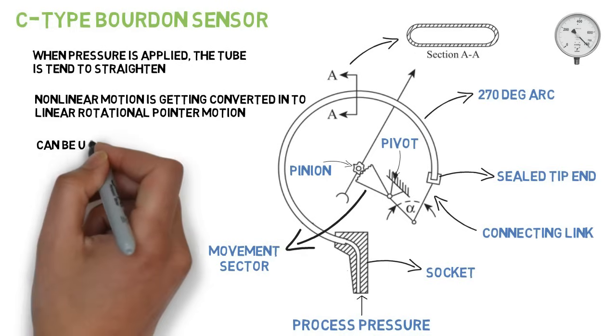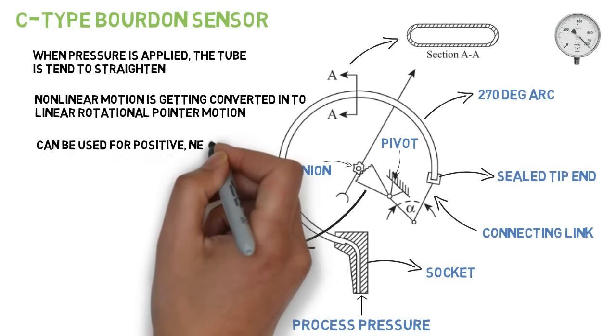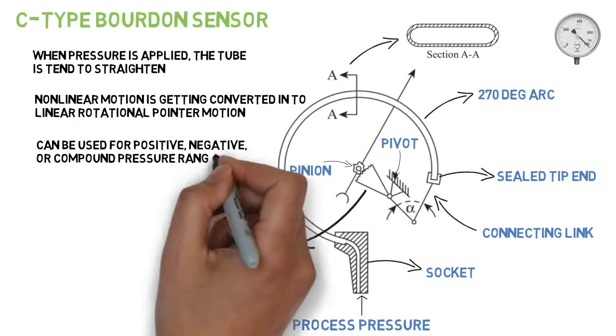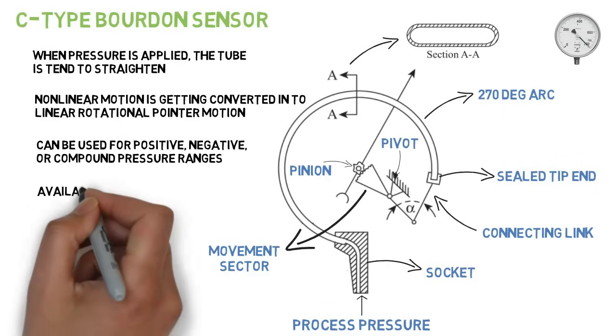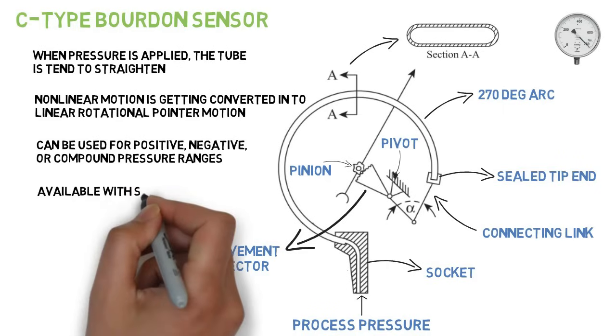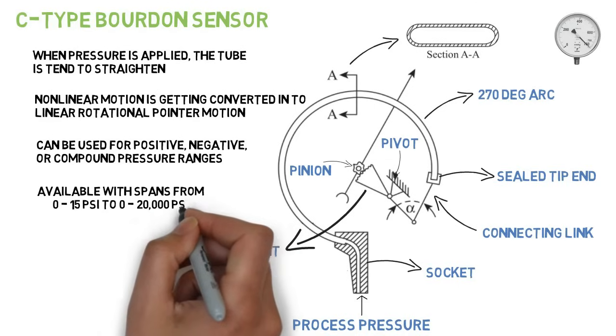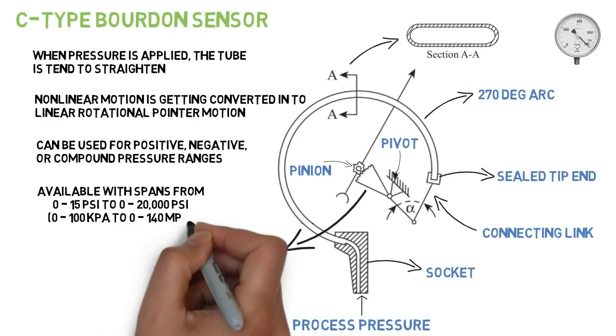C type Bourdon tube elements can be used for positive, negative, or compound pressure ranges, but the indication on the vacuum side will not be accurate or sensitive. C type Bourdon tube elements are available with spans from 0 to 15 psi to 0 to 20,000 psi.